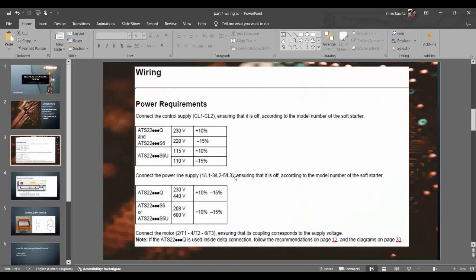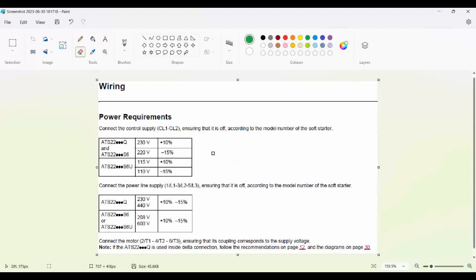Power requirements. Connect the control supply, CL1 CL2, ensuring that it's off, according to the model number of the soft starter as shown in the table below. In the tables below, we have the ATS22Q rated for 230V/220V with a tolerance of plus 10% and minus 15%. This means the soft starter can tolerate a voltage increase of up to 10%. Let's calculate it. 10% of 230V is 23V. Adding this to 230V gives you 253V. Therefore, if the voltage exceeds 253V, the drive may fail.